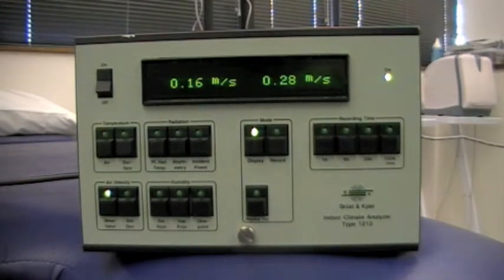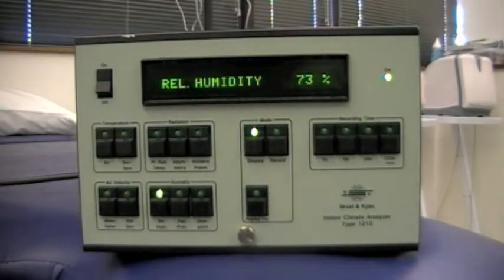With the air conditioner on you can see now the air movement, the air velocity and it's gone up considerably. So we're now on an average of 0.27 meters per second which is really good for general indoor comfort.